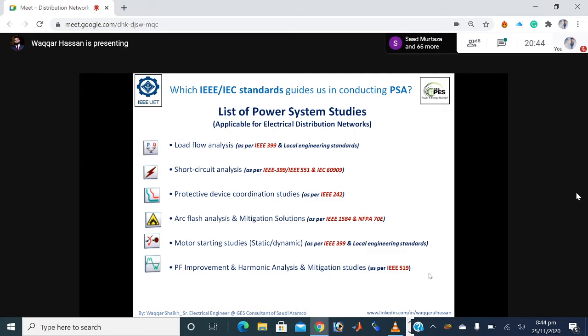Similarly, for protection coordination study, there is IEEE standard 242. For arc flash analysis and mitigation solutions, we refer to IEEE 1584 and NFPA 70E standards. For motor starting, IEEE 399. For power factor correction studies or harmonic analysis, we follow the IEEE 519 standard.